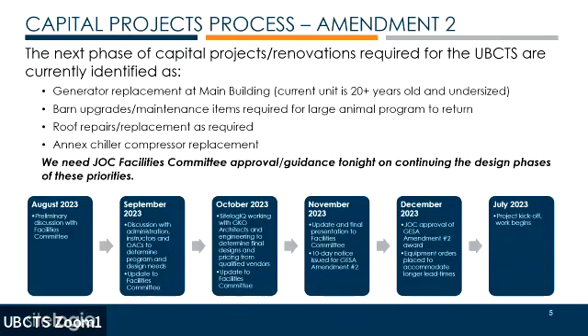Here's the question I would ask the manufacturer: they warranty those for what, 10 years? Depends on the product, probably 5 to 10 years. So by purchasing them staggered the way we are, does that affect the warranty? If it doesn't void it, that's something the manufacturer suggests but doesn't necessarily void. I can't see throwing away a $20,000 compressor.